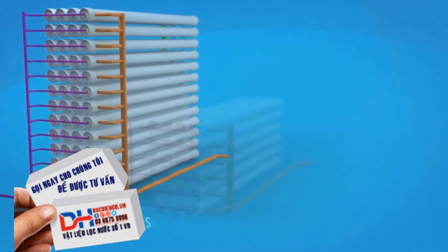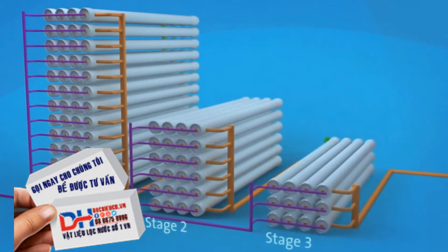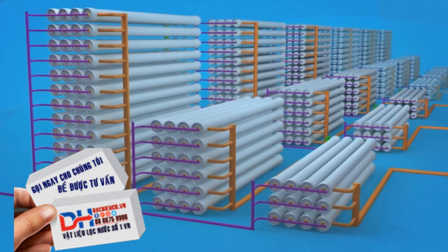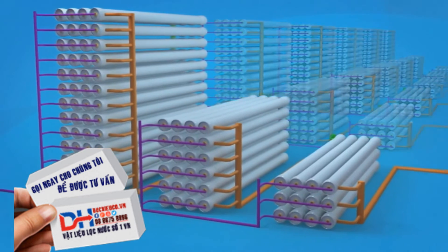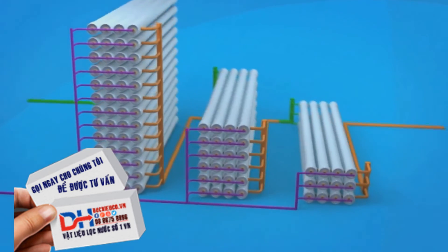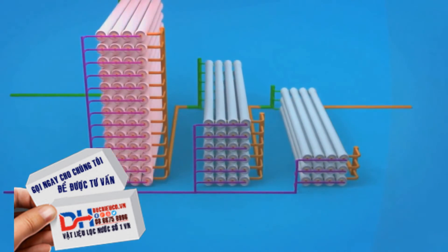At St. Mary's, there are six reverse osmosis treatment trains, each with three stages. This design produces the highest amount of recycled water with reduced concentrate waste. Stage 1 has 52 pressure vessels, Stage 2 has 24 pressure vessels, and Stage 3 has 12 pressure vessels.